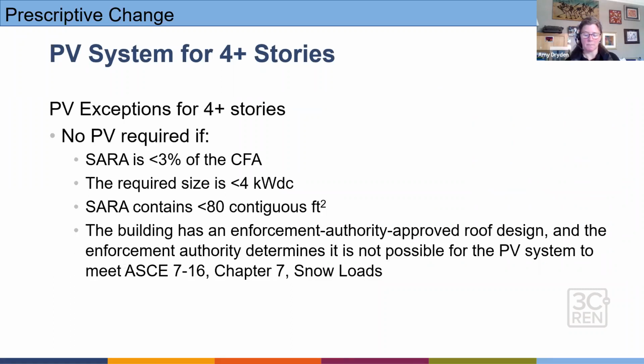Next slide. Oh, sorry. So a couple of exceptions that we'll see here for the 4+ stories. If that solar access roof area is less than 3% of the conditioned floor area, then I have that exemption. If the required size is less than 4 kW, then I'm exempt. If I have less than 80 contiguous square feet, so it's just not enough area that is viable in terms of, it's viable for producing PV, but from a cost effectiveness standpoint, it's not a large enough area, then I'm exempt. And there can be exemptions through different roof designs and also snow loads that may allow a project to be exempt from the prescriptive PV.